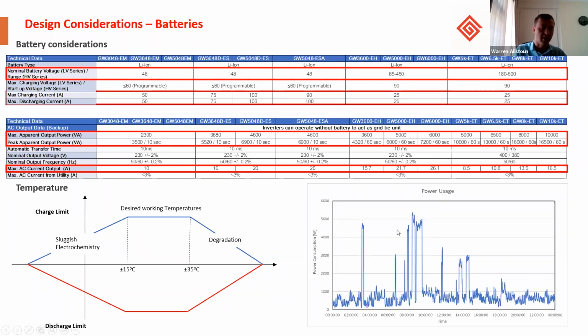So if we had to look at the load example again, the peak here specifically, we call it 5 kilowatts. To deal with that peak on a low voltage product, we would need 100 amps. And to achieve 100 amps, we need to look at each battery and understand what each battery can deliver in terms of current, so that we can stack enough batteries to deliver the loads.